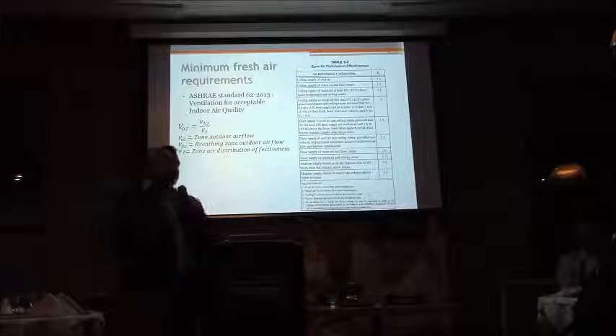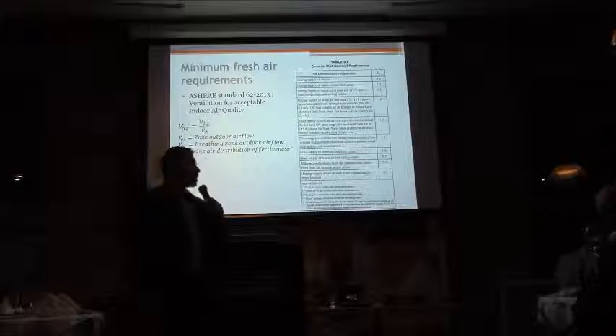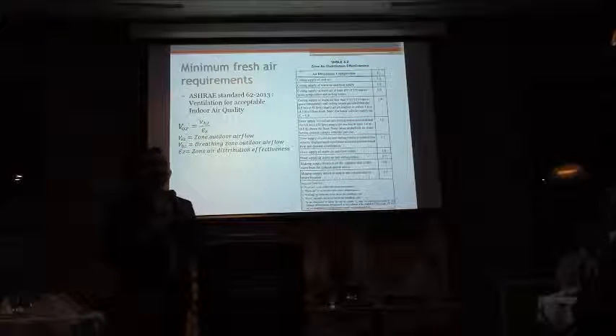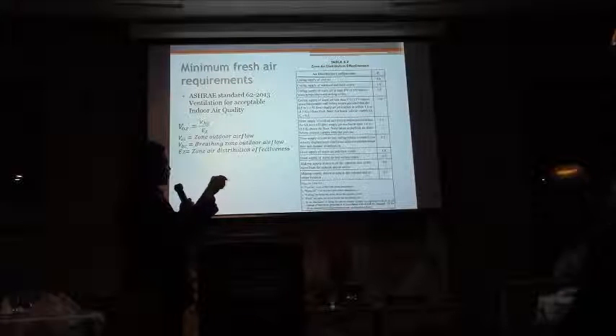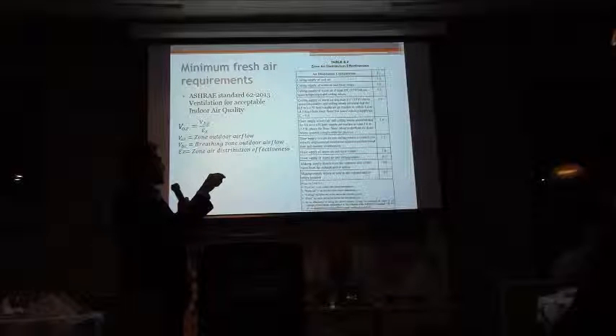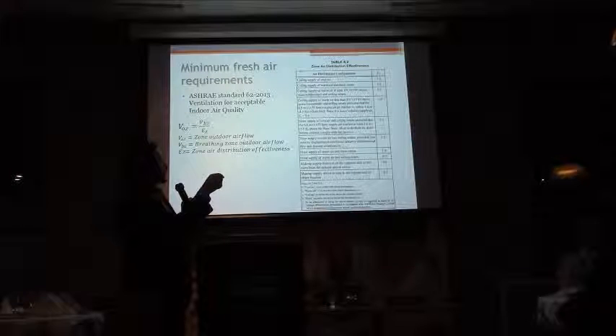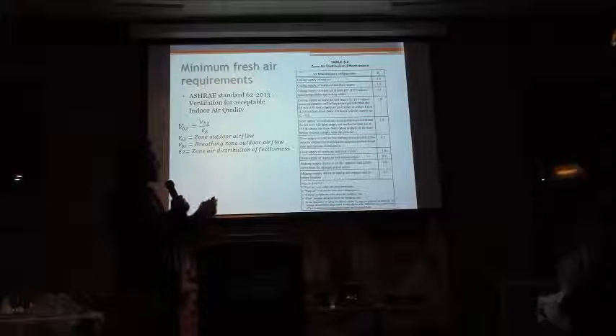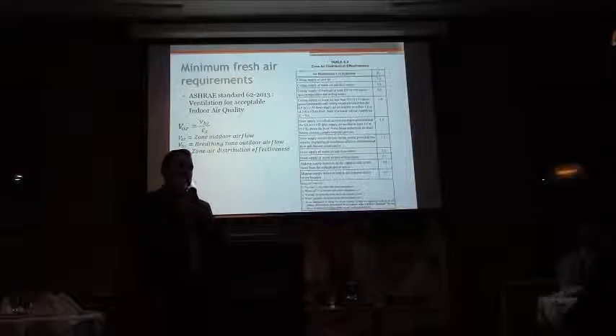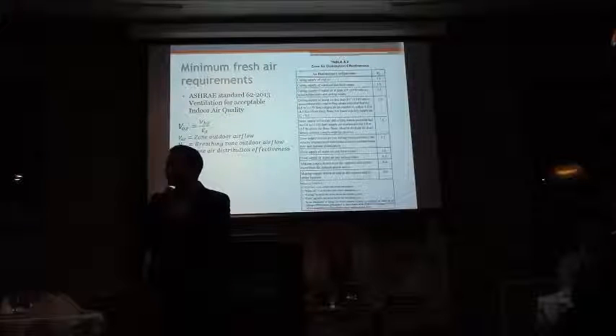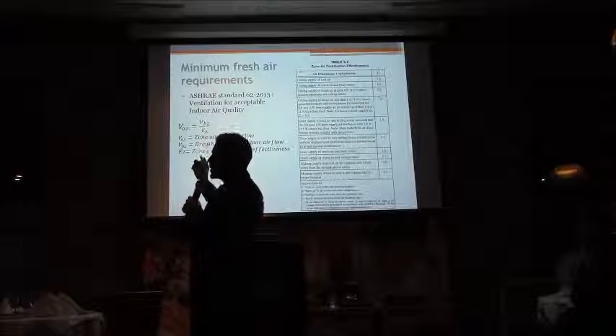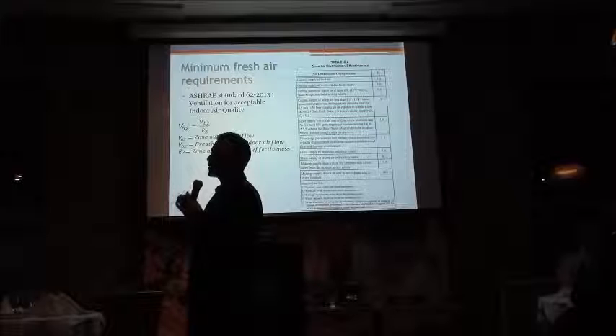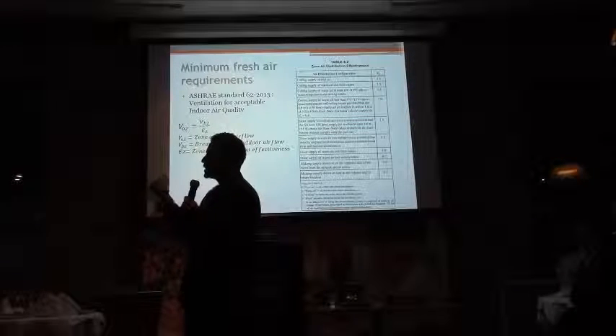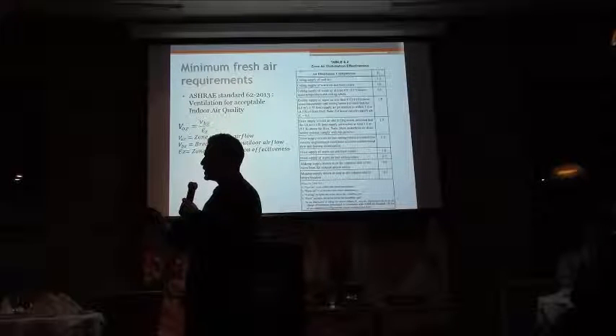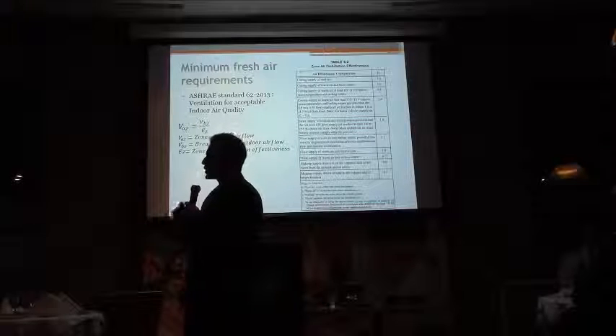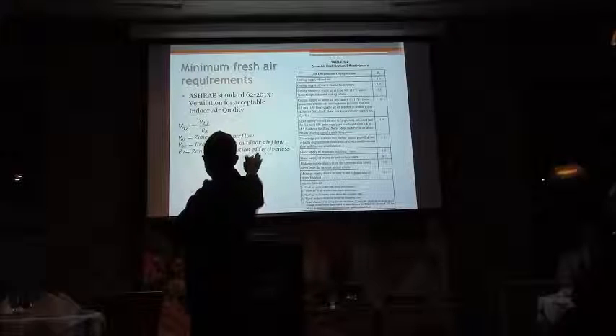So because of that, like I mentioned, you have some of your hot air that's bypassed into your return. What happens is that in ASHRAE Standard 62, whenever we do our fresh air calculations, ASHRAE says here, line number 3, if you're supplying air through the ceiling at least 8 degrees Celsius above space temperatures and ceiling return, your EZ, your zone air distribution effectiveness factor, is 0.8. So that means if you calculate a certain amount of fresh air, let's say 1,000 CFMs, you need to divide that by 0.8. So that means you're at 1,250 CFMs of fresh air. That's an added 250 CFMs of fresh air that you need to heat or cool, humidify, dehumidify. So you need to treat all that fresh air, and there's a cost related to that. So if you can reduce the amount of fresh air, that's energy savings.